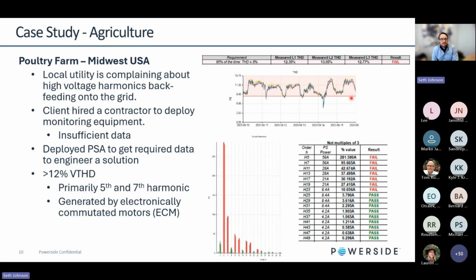And this was basically a poultry operation or a poultry farm, and there were hundreds of motors in there powering fans in these barns. And there were, I think, 6 different barns total at this facility. Now, these motors are what are called ECM motors, so electronically commutated motors, which have what is similar to a 6-pulse drive spectrum, essentially, which basically produces harmonics.